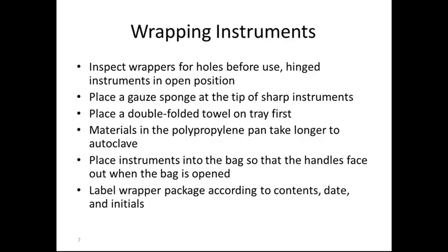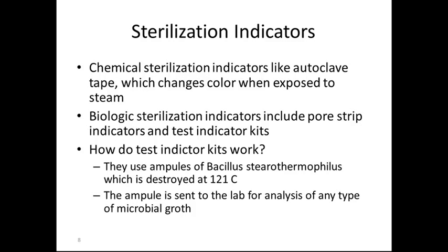Material in the polypropylene pan takes longer in the autoclave. Place instruments into the bag so that the handles face out when the bag is opened. Label the wrapper package according to the contents, the date that it was sterilized, and your initials. All packages should have sterilization indicators.